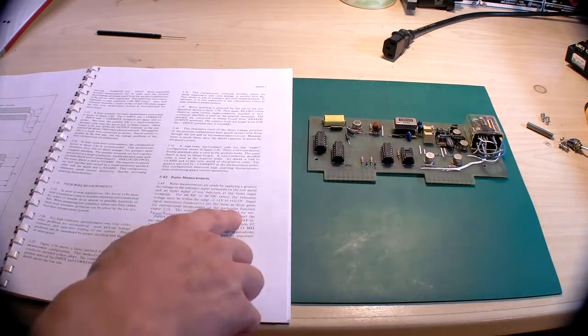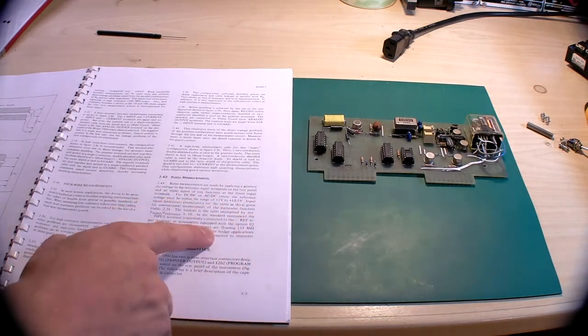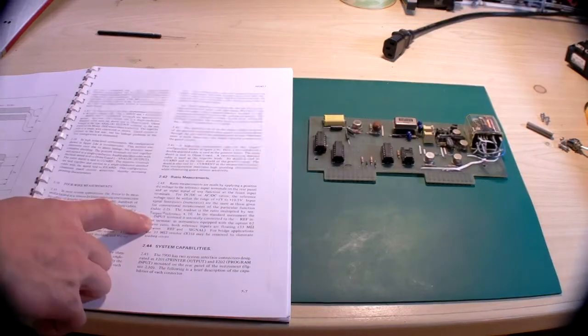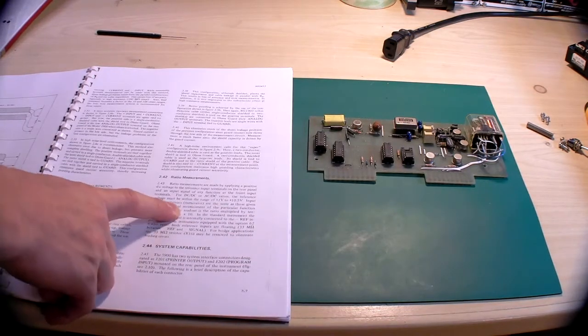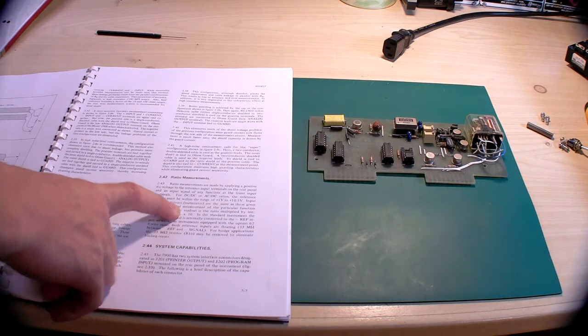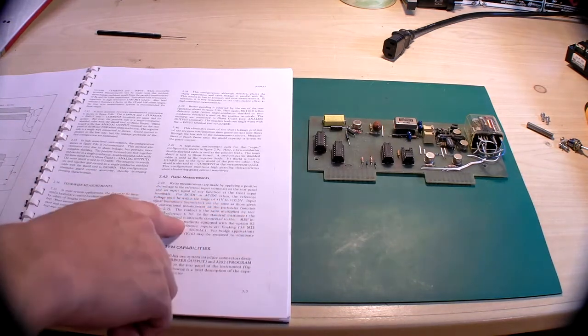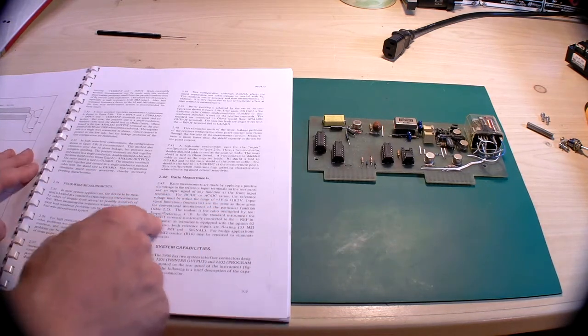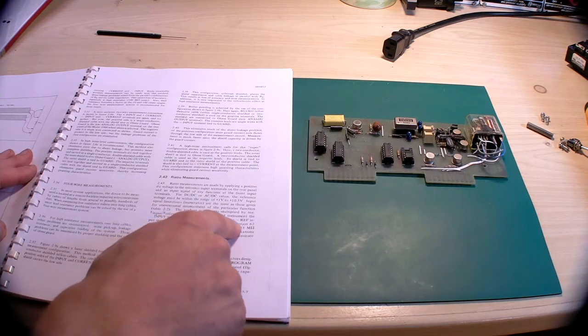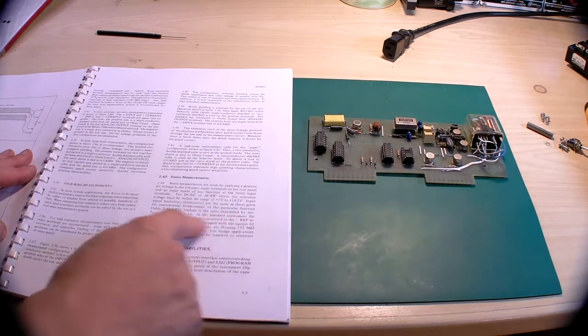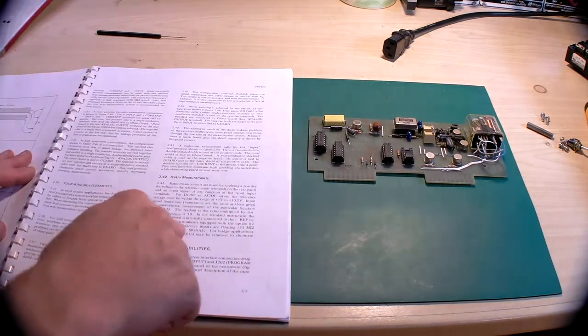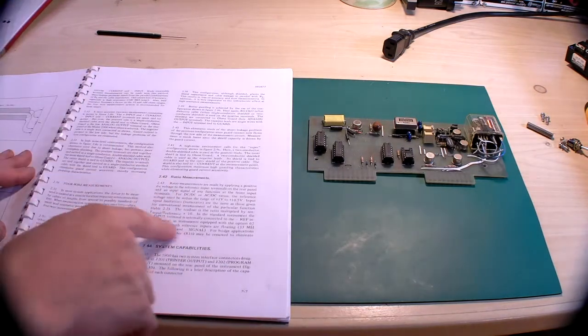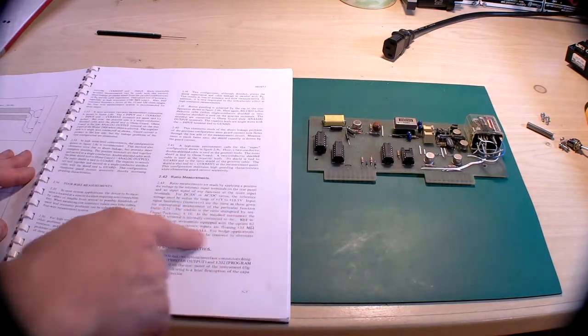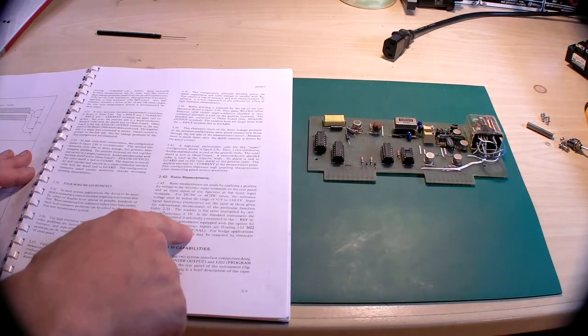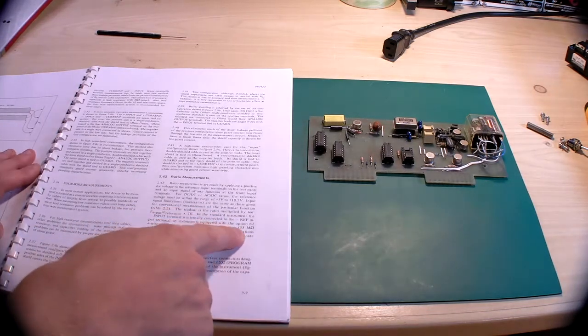The readout is the ratio multiplied by 10: input over reference, times 10. In the standard instrument, the minus input terminal is internally connected to the minus reference input terminal, but in my example with option 62, both reference inputs are floating.